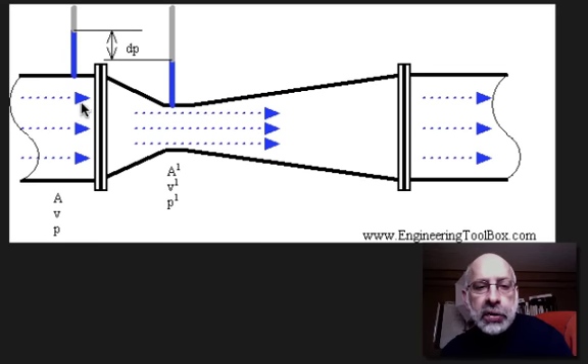So, as the flow enters here, it accelerates to get through the throat. Because the fluid is increasing its velocity, it drops its pressure. And you can see there's a piezometer here and a piezometer here, and there's a differential pressure with low pressure being back at the throat.